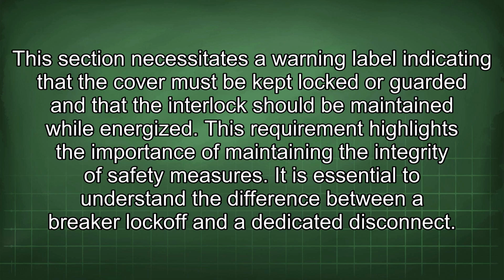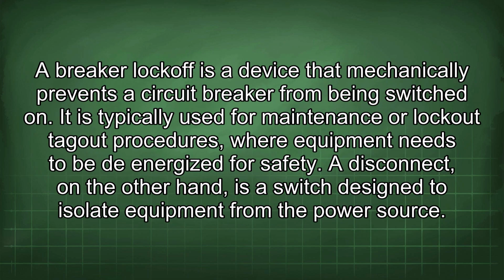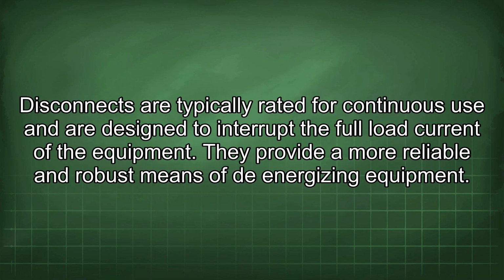It is essential to understand the difference between a breaker lockoff and a dedicated disconnect. A breaker lockoff is a device that mechanically prevents a circuit breaker from being switched on. It is typically used for maintenance or lockout-tagout procedures where equipment needs to be de-energized for safety. A disconnect, on the other hand, is a switch designed to isolate equipment from the power source. Disconnects are typically rated for continuous use and are designed to interrupt the full load current of the equipment. They provide a more reliable and robust means of de-energizing equipment.